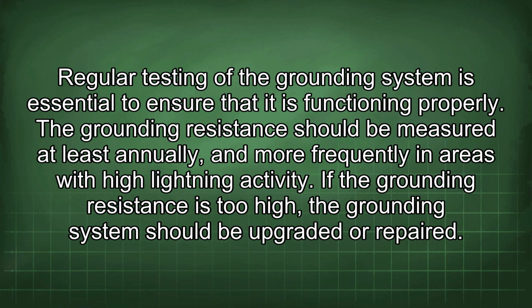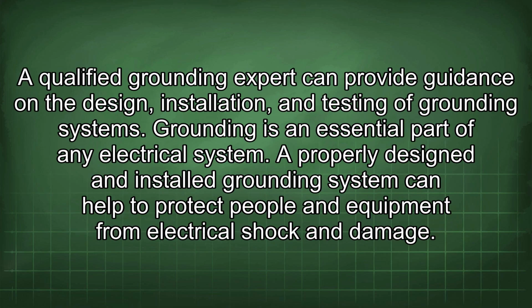Regular testing of the grounding system is essential to ensure that it is functioning properly. The grounding resistance should be measured at least annually and more frequently in areas with high lightning activity. If the grounding resistance is too high, the grounding system should be upgraded or repaired. A qualified grounding expert can provide guidance on the design, installation, and testing of grounding systems.